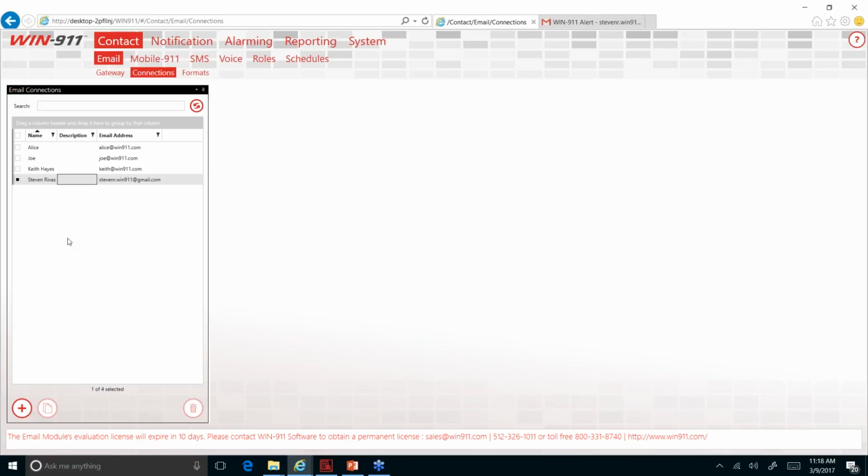For FactoryTalk 9, we support FactoryTalk 9 now. So if you're using it, you can use Win911 with it. I will say that I need to create an app note for FactoryTalk 9. So if you are using FactoryTalk 9, you'll need to make some changes to the alarm and event service that runs on that system. You need to change the logon user from what it's set to now, which is local service, to local system, in order for the connection to work properly. So if your question is you've tried that already and it didn't work, that's the change you need to make to make it work.